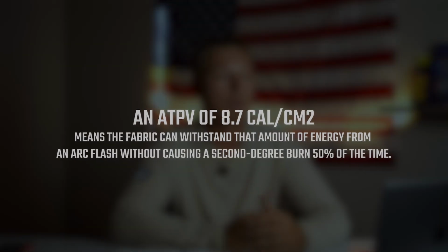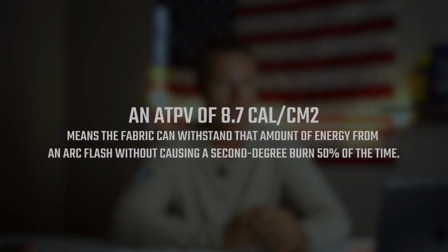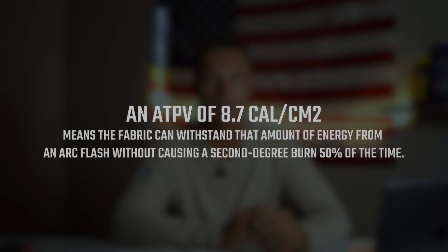Now, you'll have category 1, 2, 3, and 4, and I'll explain what those all mean exactly and the importance of those. But all our FR has an arc rating to protect us from arc flashes. Exactly like if this shirt is rated for 8.7 calories per square centimeter, that means this fabric can withstand the amount of energy from an arc flash without causing a second-degree burn 50% of the time. Basically, that means this fabric is pretty good. It's going to protect me for the most part.